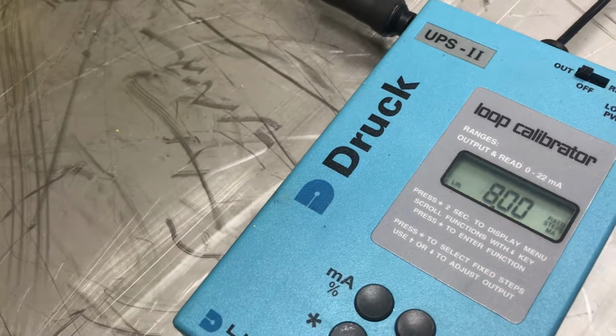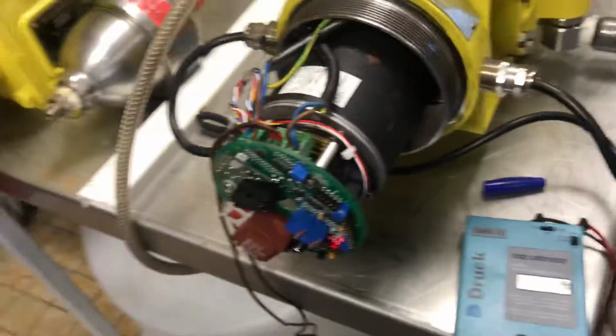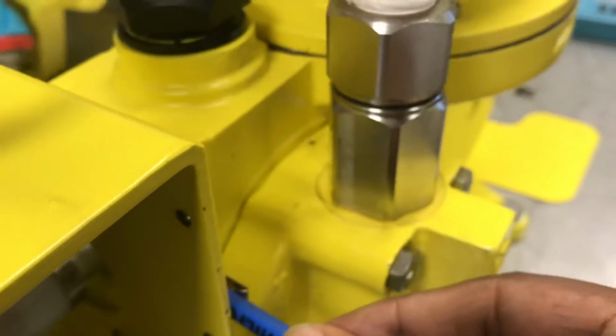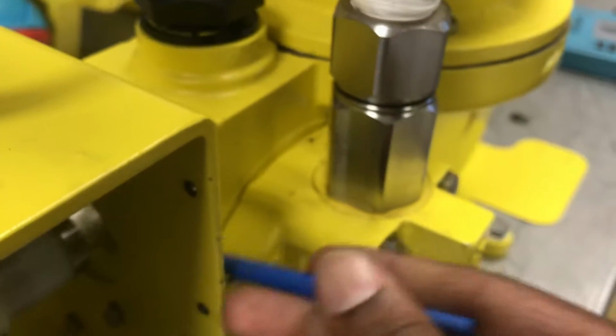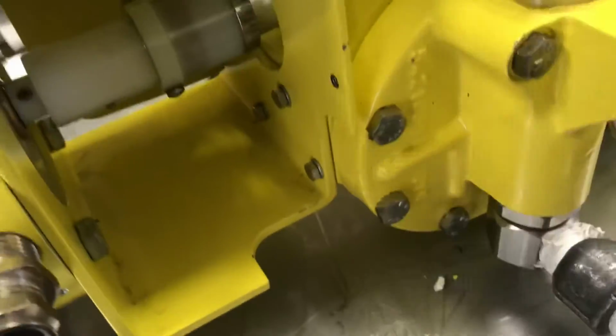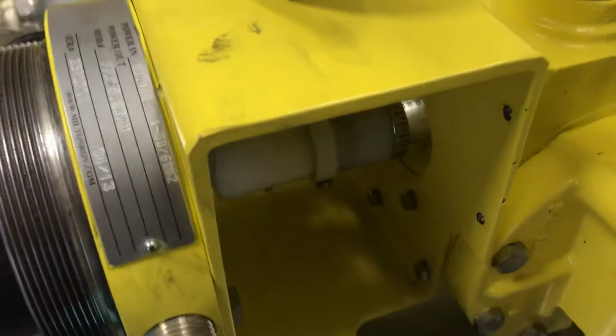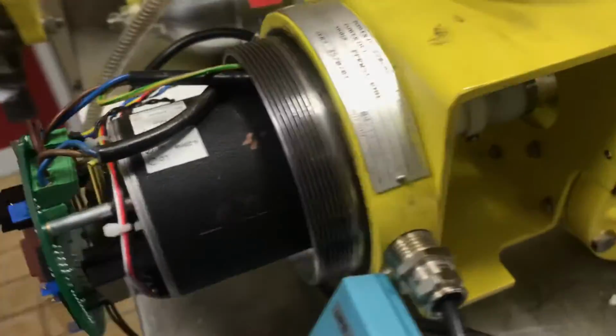Now we have set the actuator, but please make sure that the proper 100% and 0% are there. Even though we calibrate 0 to 10 turns, if you have difficulty in this connection, for example, sometimes maybe a little turn will be more. Once you connect it, you can again adjust with the same method. Make sure that it is connected and it is matching the exact stroke length. Okay, that's it. If any doubt, you can see the manual also.